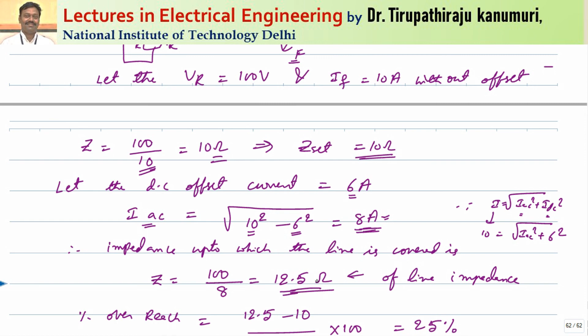In practice, the percentage overreach is taken between 10% to 20%. This problem happens only because of high speed distance relays, which operate instantaneously in the first 2-3 cycles. If the distance relay operates after 2-3 cycles, by that time the DC component will die out, so it will measure the actual value and this overreach problem will not come. That's why high speed distance relays are generally used for zone number 1 of your protection. That means the zone starting from your alternator, the first zone.